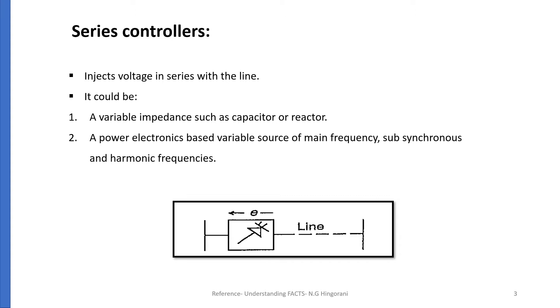Series Controllers are used to inject voltage in series with the line. The series controller could be a variable impedance such as capacitor, reactor, etc., or a power electronic based variable source of main frequency, subsynchronous frequency, or harmonic frequency. Voltage injection in series with the line is represented by a variable impedance multiplied by the current flow through it. Series controller supplies or consumes variable reactive power when the supplied voltage is in phase quadrature with the line current. Any other phase relationship involves handling of real power as well.